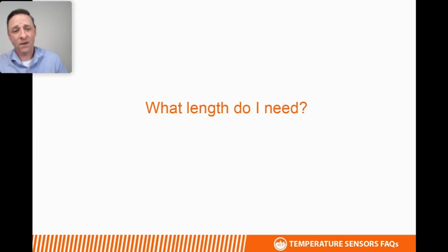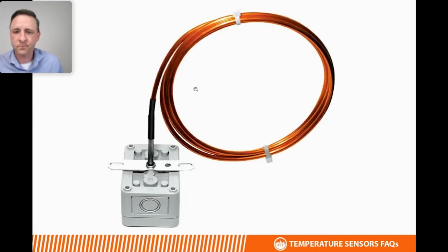So for averaging sensors, the most common question is what length do I need of that element? And we recommend using 1 foot of element for every 1 square foot of the duct cross section. So just measure up the cross section, the length and width of the duct, get your cross section square footage, and use 1 foot of averaging sensor per 1 square foot of that cross section.